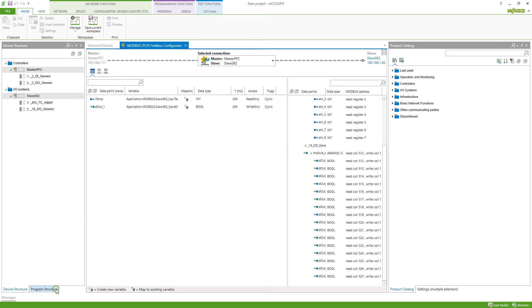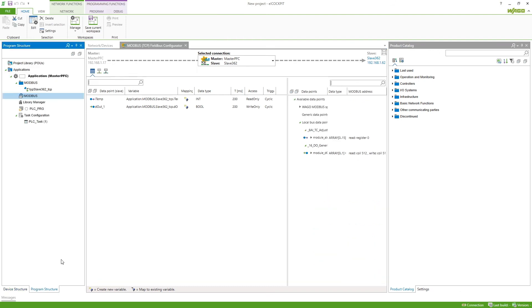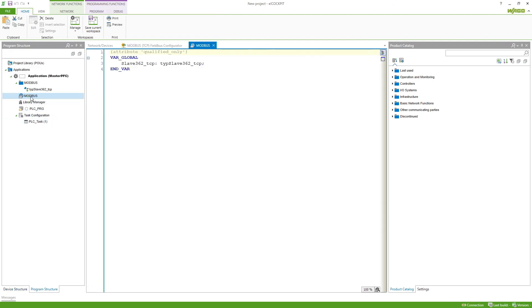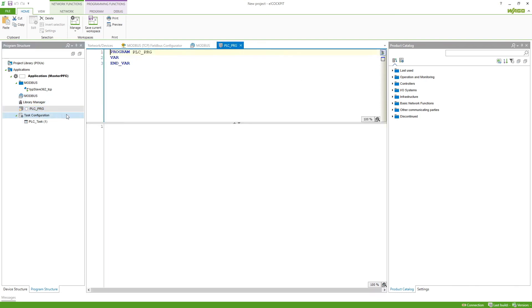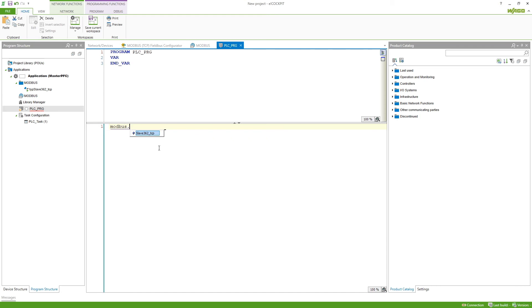Now we can already go to the program structure and E-Cockpit will now generate a global variable list with the name Modbus. In this global variable list all the configuration is configured so we can go into our PLC PRG and then just type in Modbus and a dot and it will give us all the available slaves that we have for this configuration.